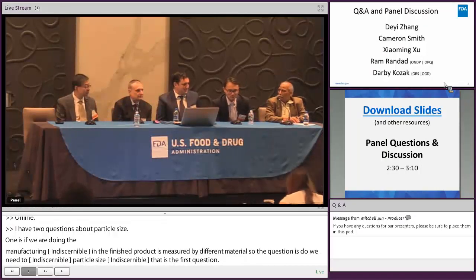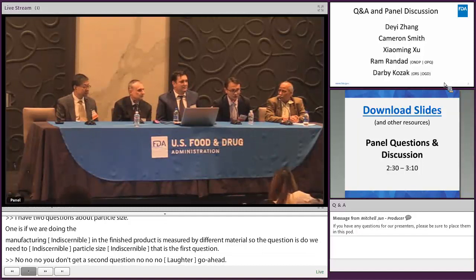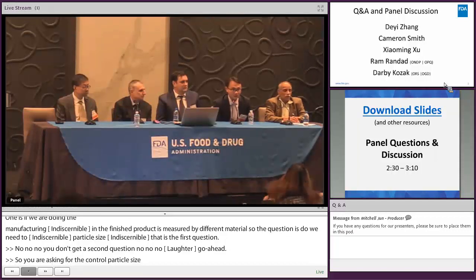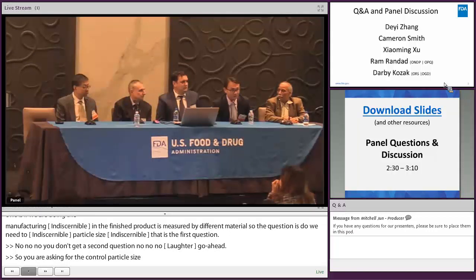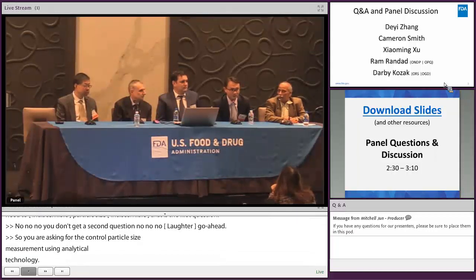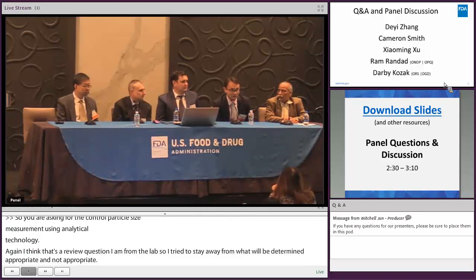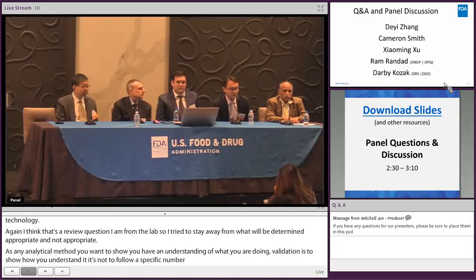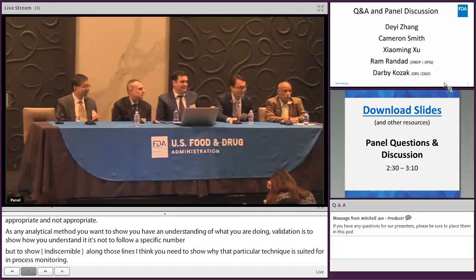Well, so you're asking about the in-process control particle size measurement using a process analytical technology, PAT. And again, I think that's a review question. So I'm from the lab, I would try to stay away from what would be determined appropriate or not appropriate. But as with any analytical method, if you want to show that you have an understanding of what you are doing, the validation is just to show how you understand it. It's not to follow specific numbers or a list of tests, but to show how you understand. So along those lines, I would think you do need to show why that particular technique is suited for in-process monitoring. It's challenging as is already for finished product characterization, and if you want to use it for in-process, that'll be more challenging. So the background to it, like in process, it's a suspension.